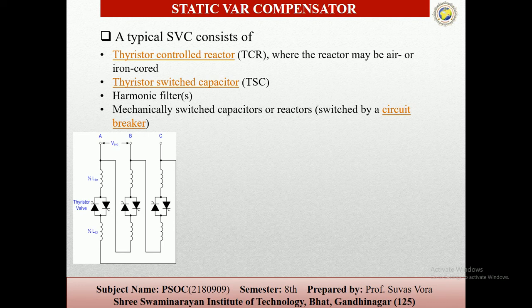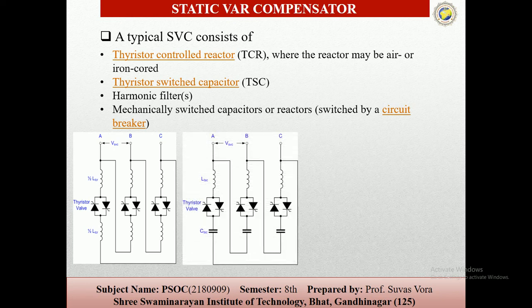Here you can see the thyristor valves we can put in the system. This one is the TCR, thyristor controlled reactor system. This one is the thyristor switched capacitor system. So these two systems have shunt connected reactor control using two parallel, oppositely connected thyristors.